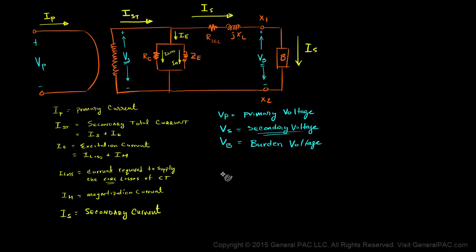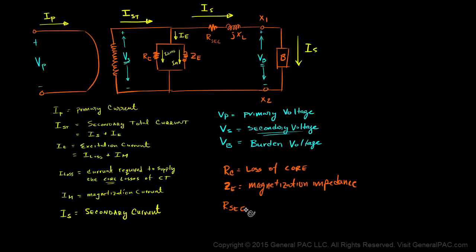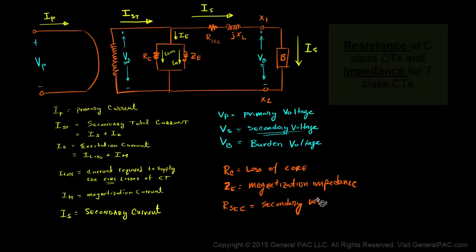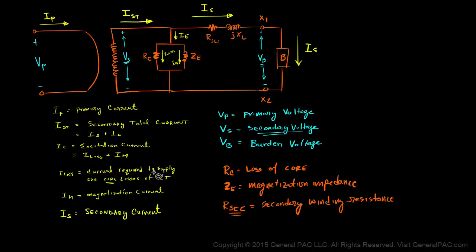Let's now move on to our impedances. RC is a resistor required to model the losses of the core. ZE is the magnetization impedance — this is the impedance that changes with respect to the secondary flux of the transformer. R-secondary is the resistance of the coil per turn; each turn has a resistance associated to it, and R-secondary models the secondary winding resistance. This value will change based on the number of turns on the secondary side. JXL is the leakage reactance — that's the small amount of flux that will not pass through the secondary winding, meaning the flux not actually reaching the core.